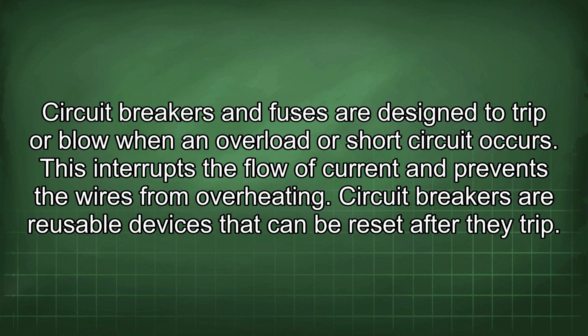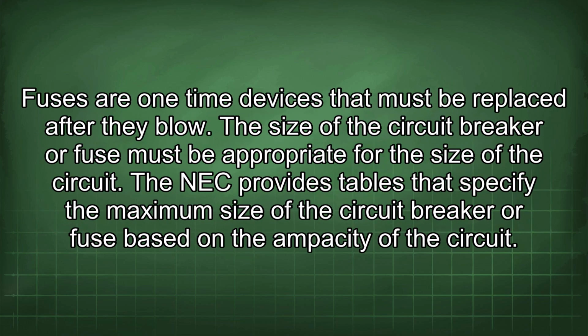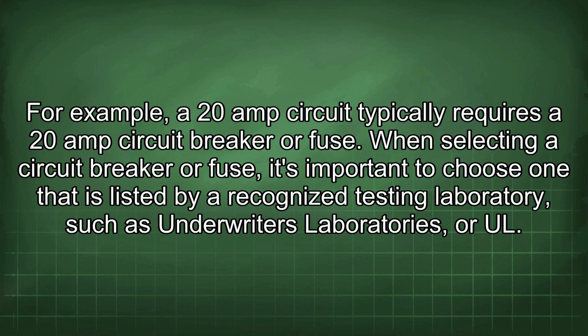Circuit breakers are reusable devices that can be reset after they trip. Fuses are one-time devices that must be replaced after they blow. The size of the circuit breaker or fuse must be appropriate for the size of the circuit. The NEC provides tables that specify the maximum size of the circuit breaker or fuse based on the ampacity of the circuit. For example, a 20 amp circuit typically requires a 20 amp circuit breaker or fuse.